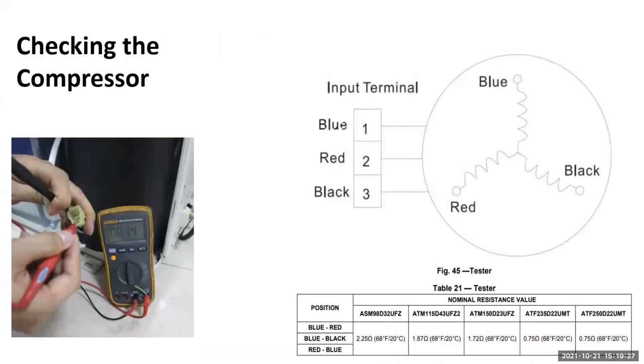And we're going to test out a compressor. Now, compressor ohm readings vary depending on the compressor and also the temperature outdoors. Well, maybe not outdoors, but usually that's where your unit is. And we're going to check these out like a 3-phase compressor. So we're looking for resistance all pretty much within 10%. We don't want to go over 10%. Now, if you want to check these through the wires, that's fine. Just take that into consideration. Always check for ground.